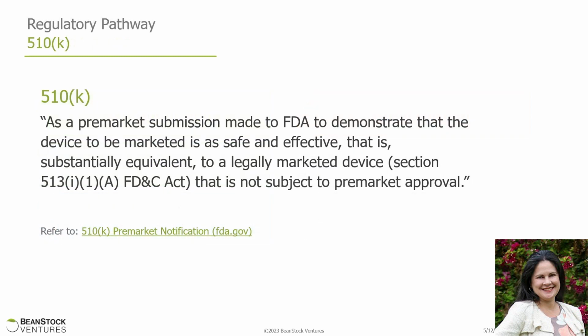The 510K is a pre-market submission made to the FDA to demonstrate that a device to be marketed is safe and effective, that is, substantially equivalent to a legally marketed device. So this means that you're showing substantial equivalency to a device that's similar or the same in intended use and similar or same in technology. This is where you're going to demonstrate to the FDA that your device is substantially equivalent to something that's already marketed.